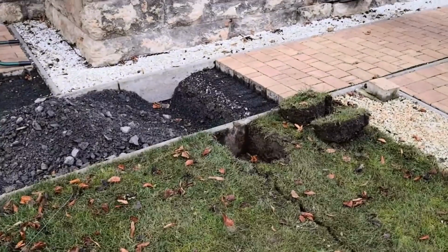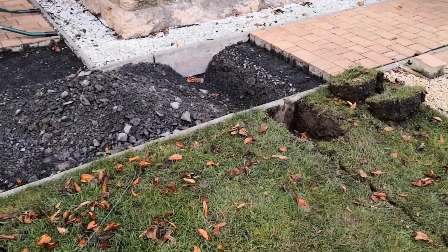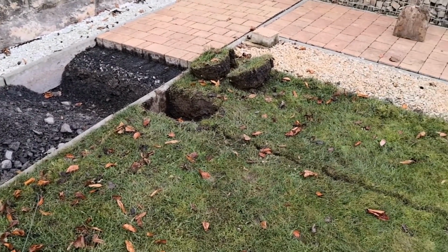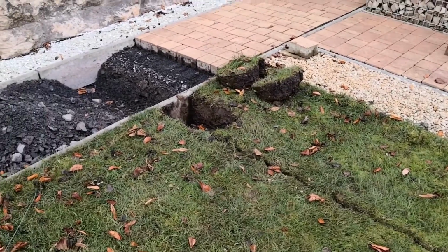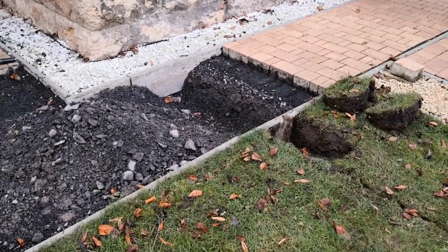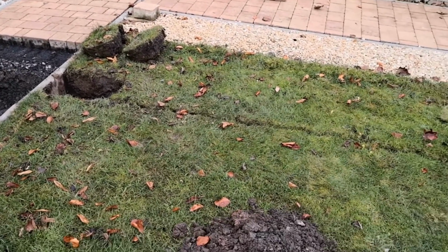Yes, my dear ones, what has happened? I have put some new electrical systems into operation, among other things a photovoltaic system on the roof of my carport. In this context, it has become clear that the existing grounding electrode, which I have been using so far for the grounding of the house, is no longer sufficient. So I have decided to install or expand the grounding electrode.